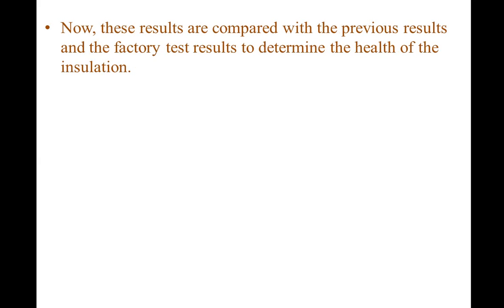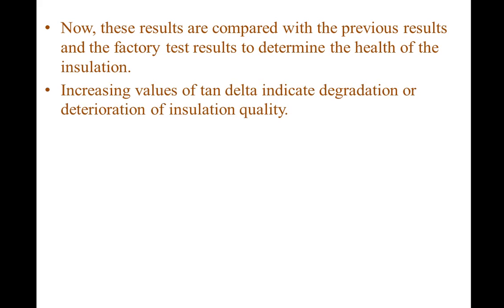The results obtained from the tan delta test are compared with the previous results and the factory test results to determine the health of the insulation. Increasing values of tan delta indicate degradation or deterioration of insulation quality.